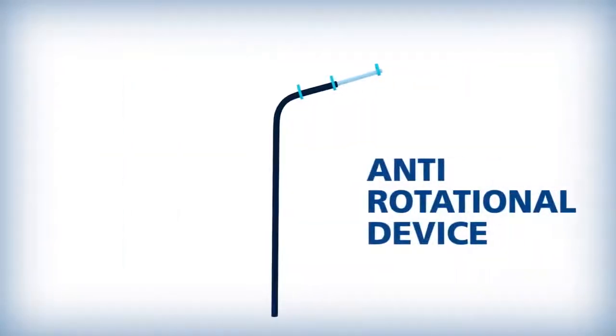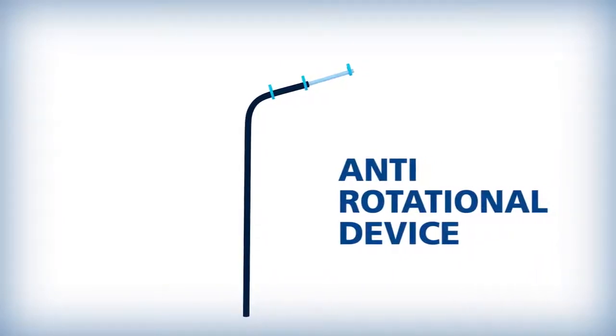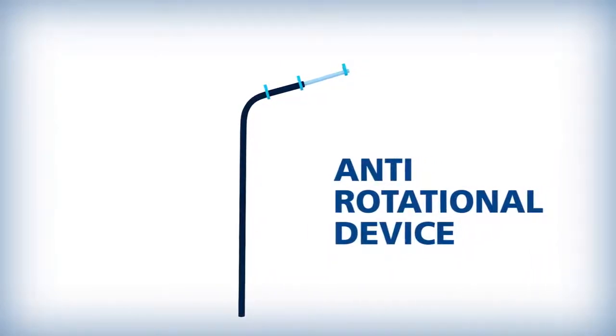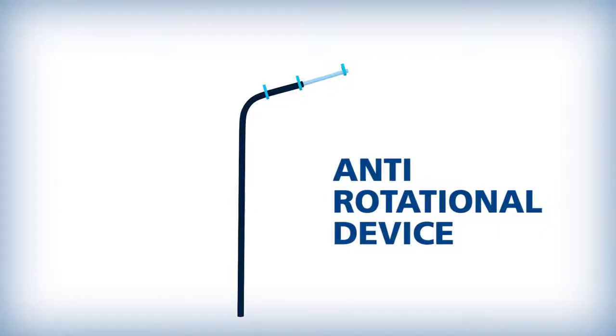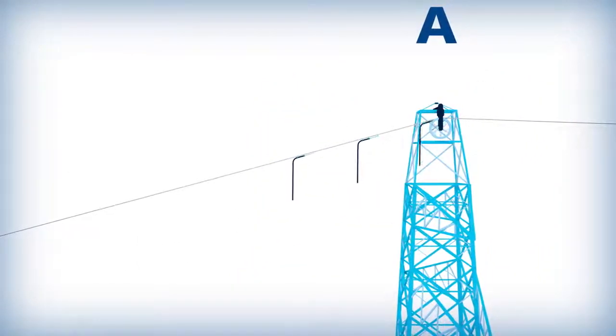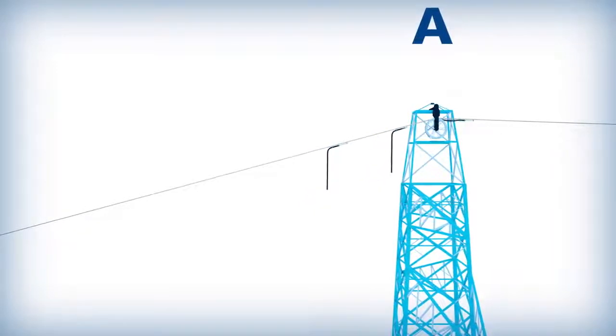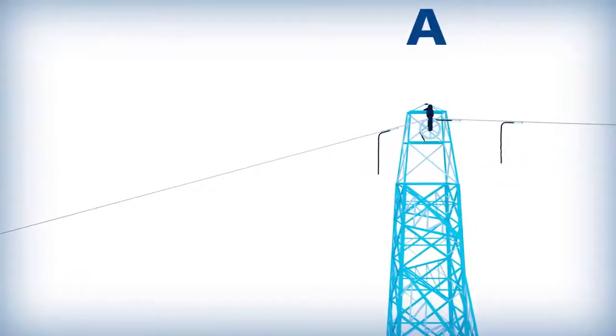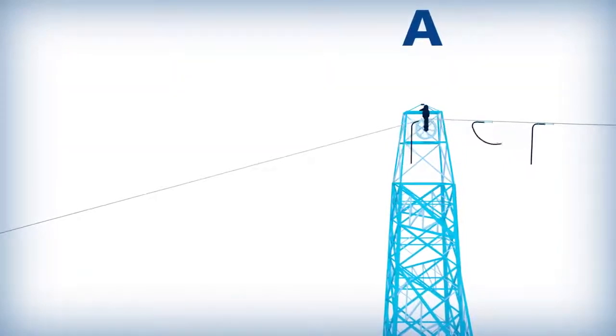AFL recommends the use of an anti-rotational device on all alumicore, centricore, and microcore designs. For OPGW installations, ARDs that attach using dummy swivels may be used, as well as ARDs that attach directly to the OPGW.